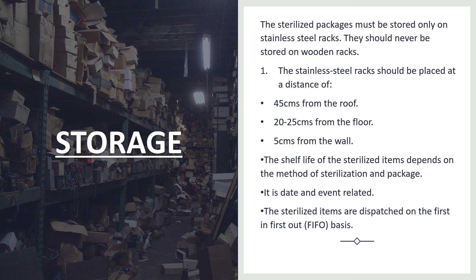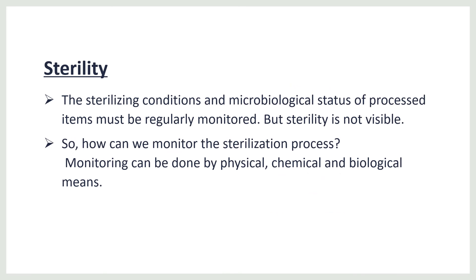Sterilized packages must be stored only on stainless steel racks, placed at a distance of 45 centimeters from the roof, 20 to 25 centimeters from the floor, and 5 centimeters from the wall. The shelf life of sterilized items is date and event related depending on the method of sterilization. Sterilized items are distributed on a first-in, first-out basis. The sterilization conditions and microbiological status of processed items must be regularly monitored, but since sterility is not visible, monitoring is done by physical, chemical, and biological means — which will be covered in the next session.